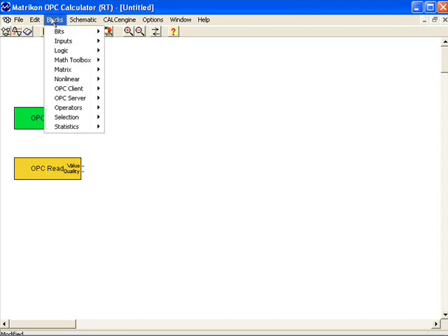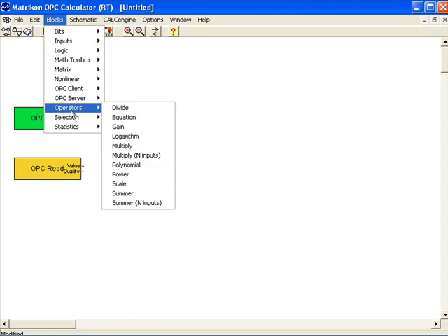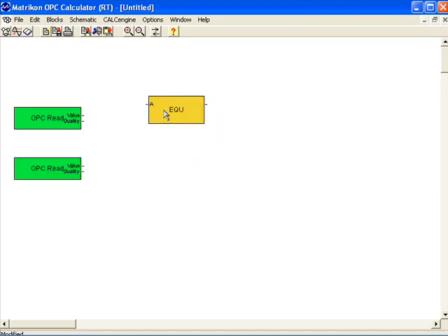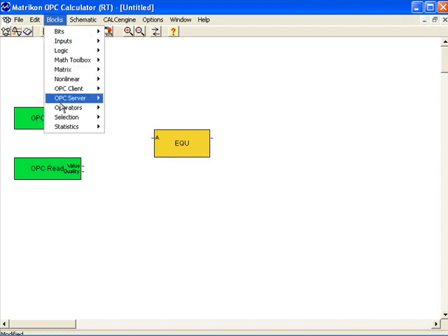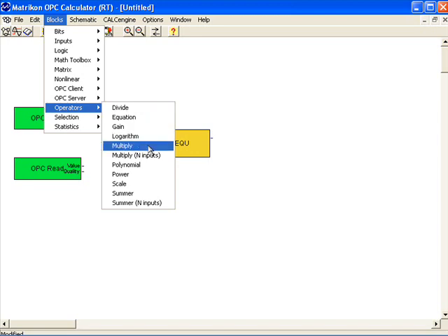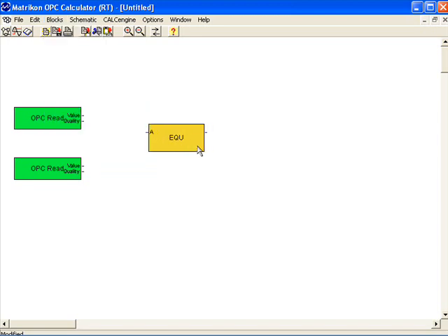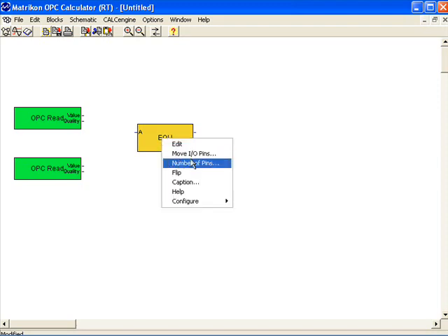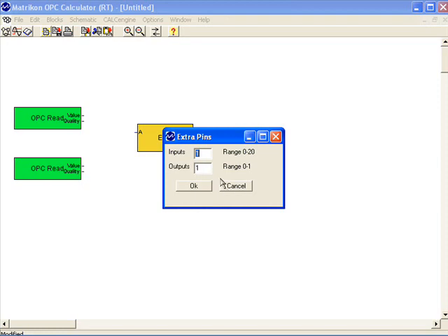Now I need to do some type of calculation, so I'm going to select a calculation block. There are many of them in this menu. For this example I'm going to use an operator block — specifically the equation block for simplicity. I can build equations one at a time using math blocks or other operator blocks, or use this equation block for a more powerful calculation. Because I have two external OPC items as data sources, I need two inputs on the left of this equation block. I right-click the block, select number of pins, and increase it from one to two.